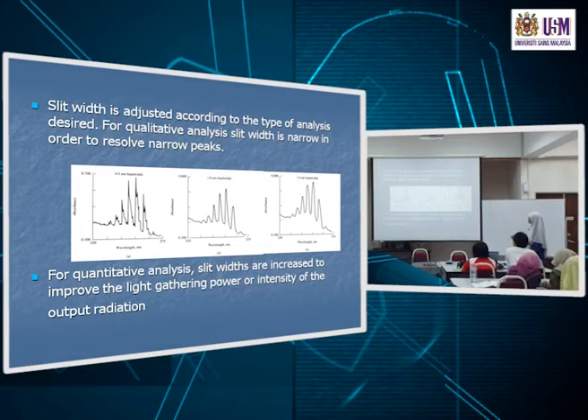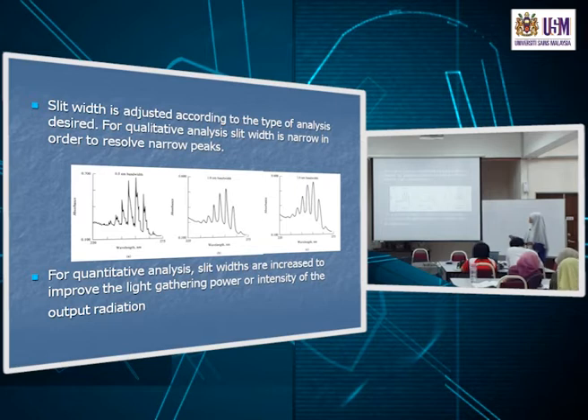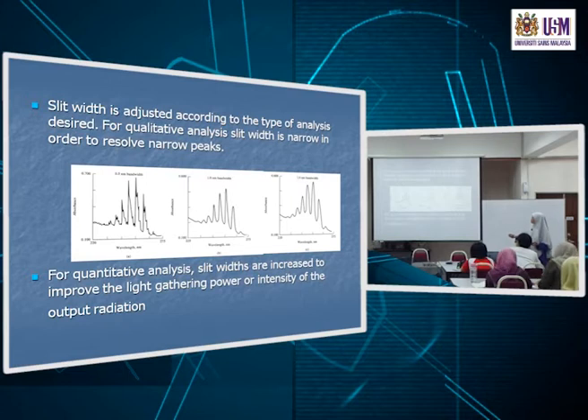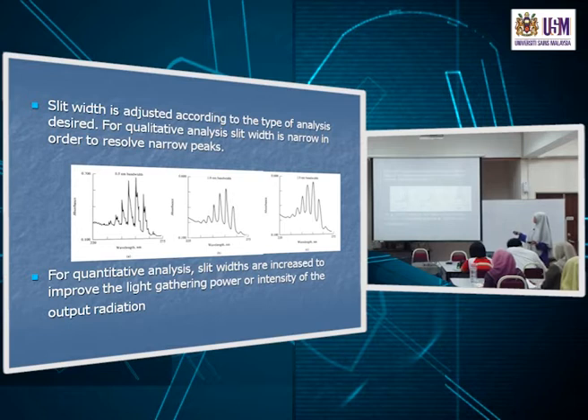Here is a band spectrum example showing bandwidths of 0.5, 1, and 2 nm — increasing bandwidth. At 0.5 nm you get good separation between the narrow peaks. As you increase the bandwidth you get some overlap, and at 2 nm the resolution is clearly not as good as with the narrowest bandwidth.